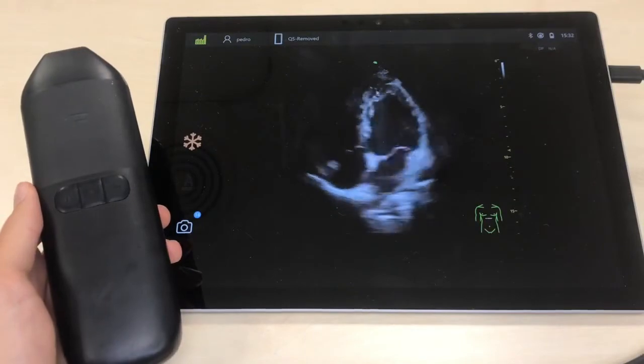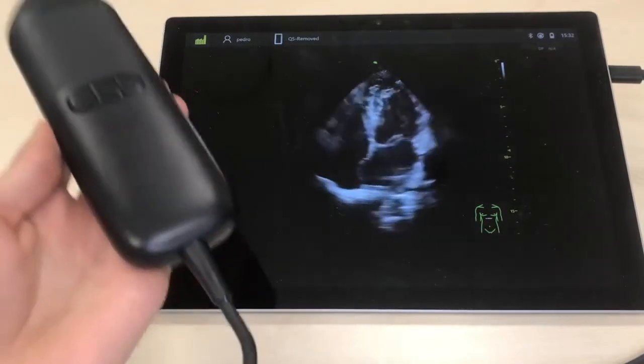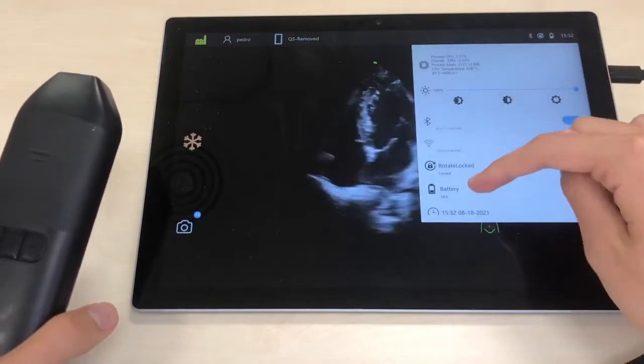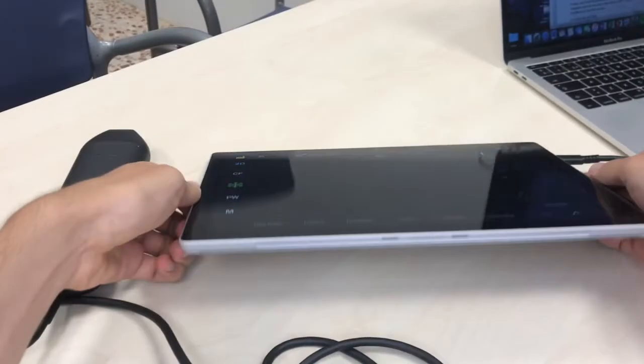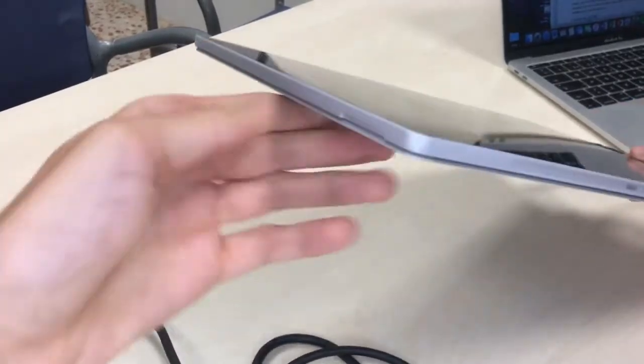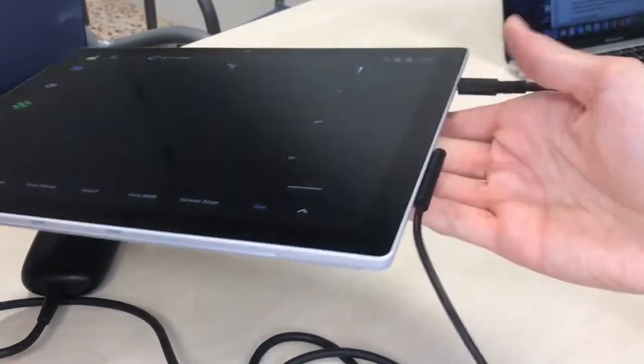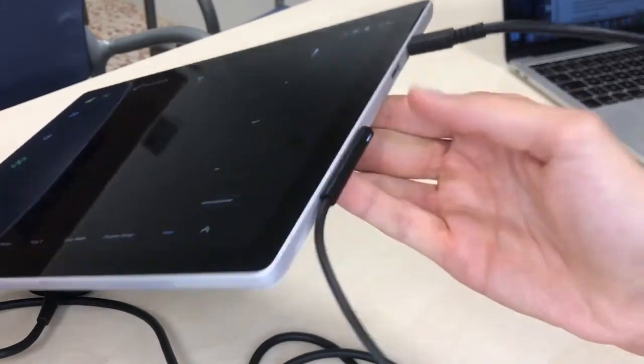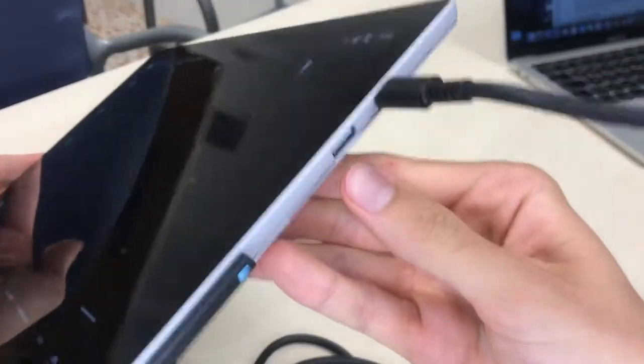Starting from the outset, as I mentioned, it is lighter than other handheld devices, mainly because it doesn't have an integrated battery, but instead it powers through the tablet's battery. This allows extended scanner autonomy, less heating, and, all in all, longer scanning sessions. Additionally, it can still be used while it's charging through this port, allowing for a whole shift of continuous scan time.